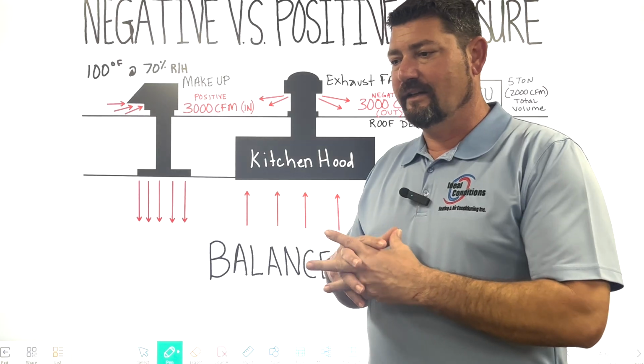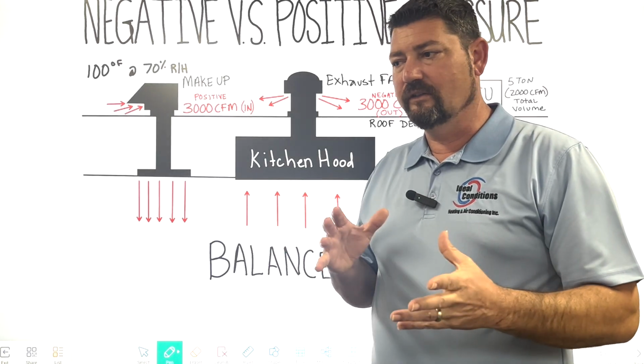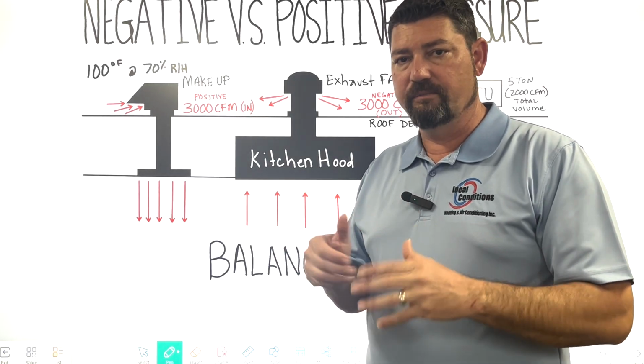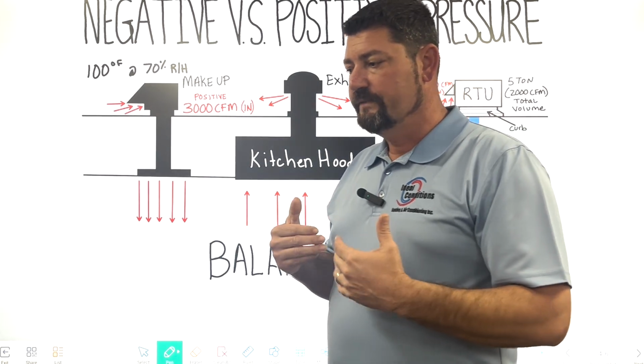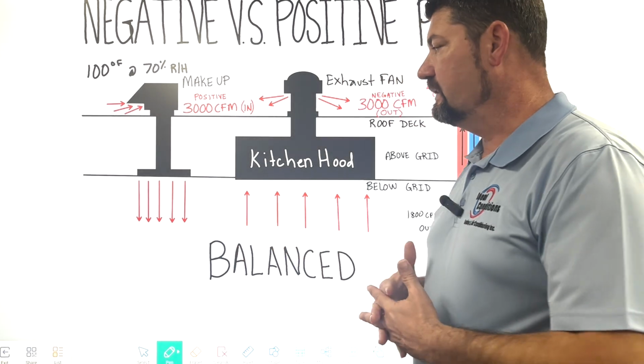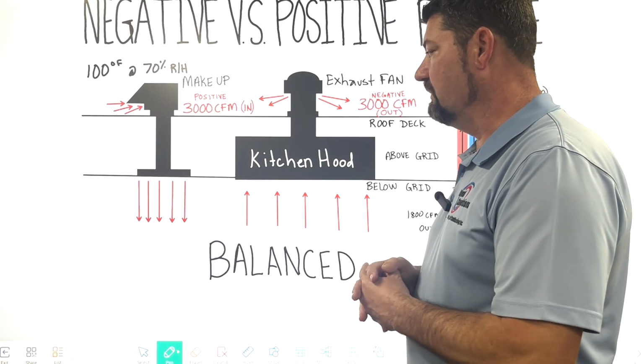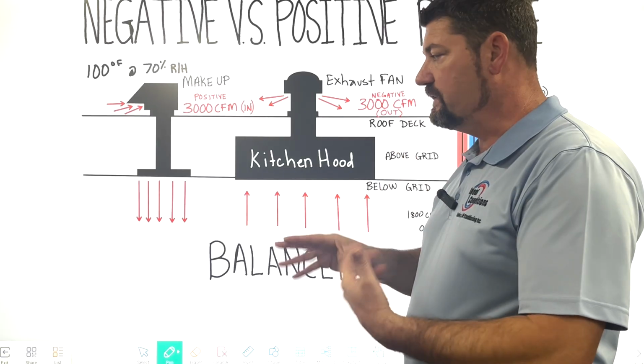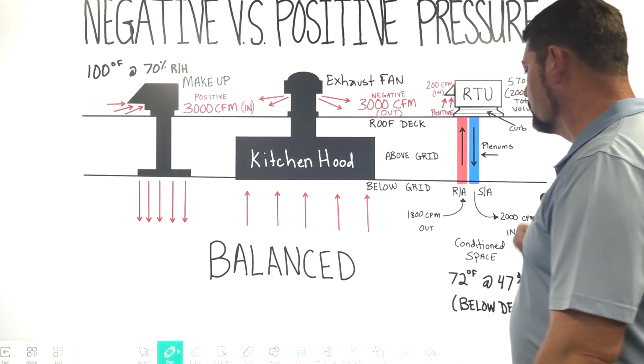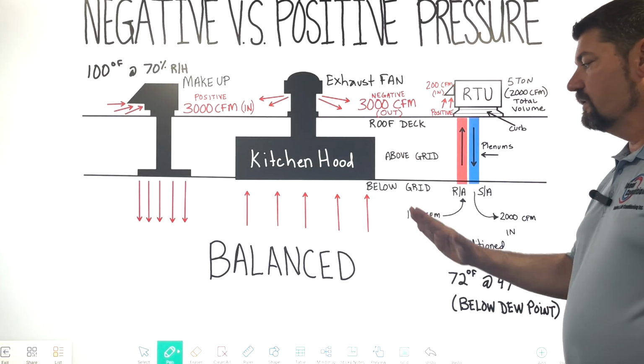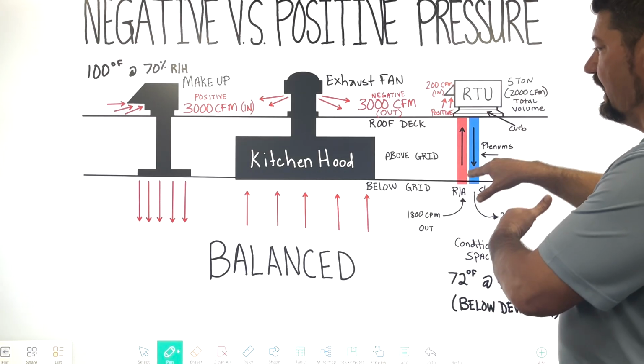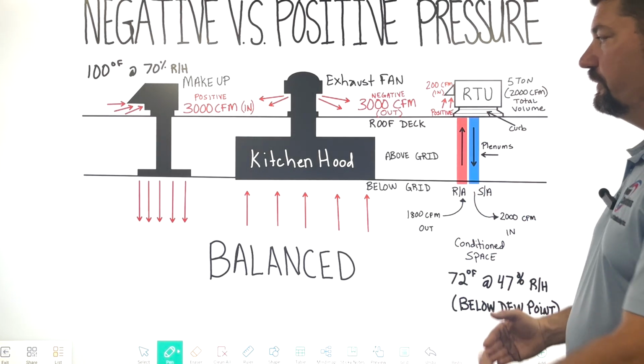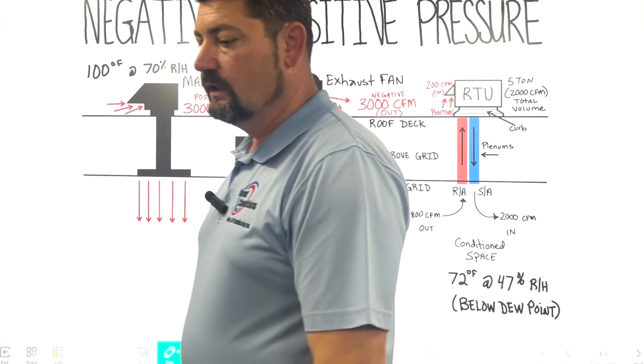And that's not a scientific thing where you can say, hey, you're balanced because the flame says so. You really want to take manometers and whatnot, and test things and make sure that a proper test and balance is done, and you're introducing more outside air than you are exhausting inside air, but through a mechanical system, not through the front door because one of these isn't working.